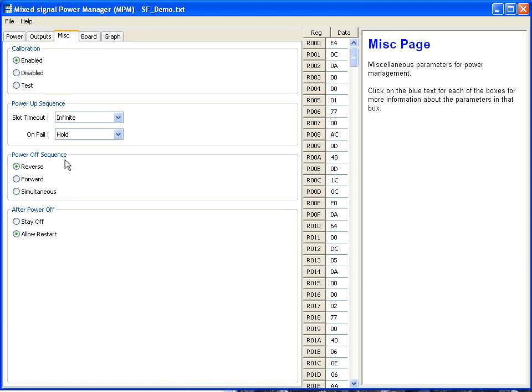The next section, for example, the power off sequence, you can choose to reverse the power off sequence, have it in the forward mode, the same as the power up, or do a simultaneous shutdown. So for a certain error flag, you may choose to shut down all of the voltages simultaneously.